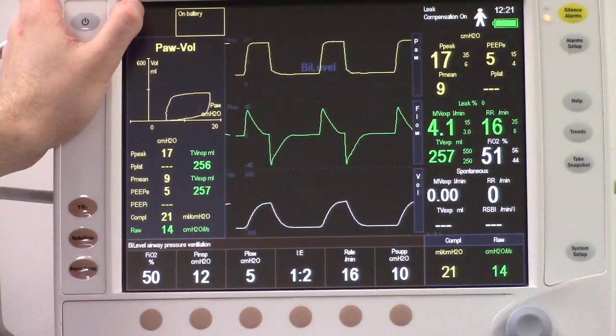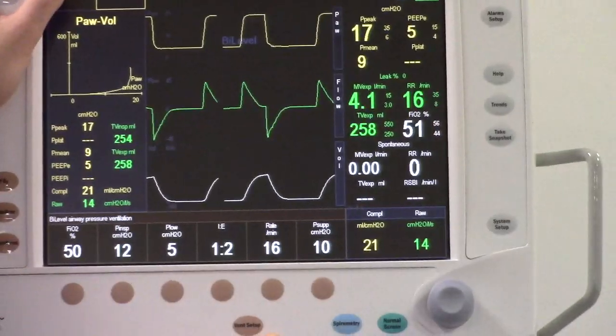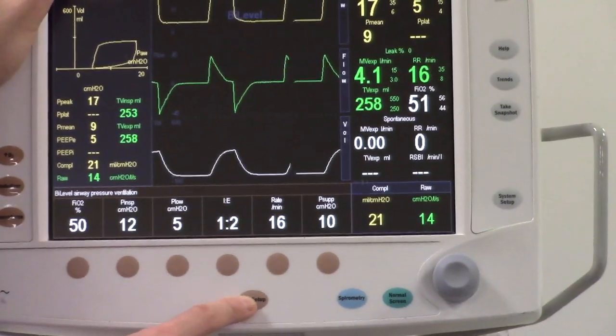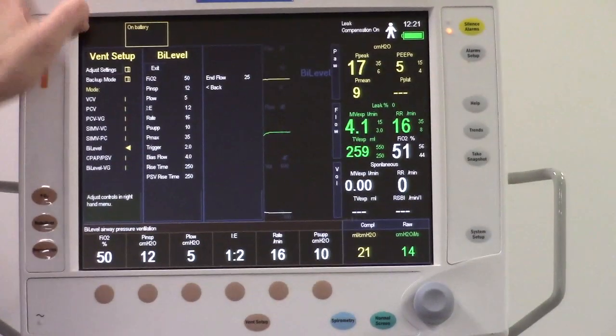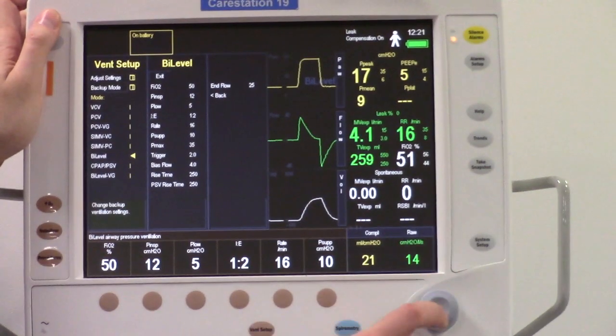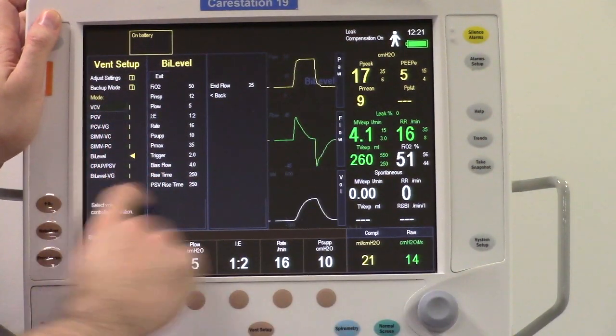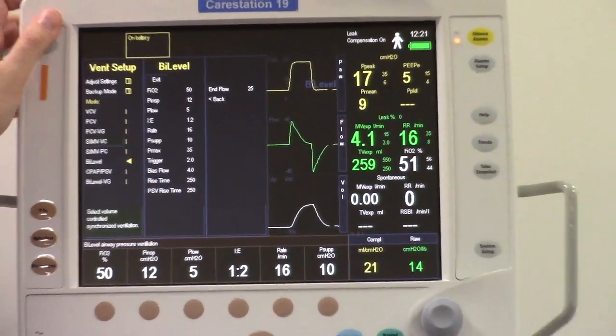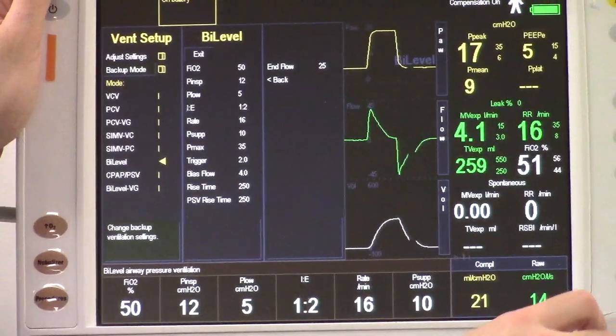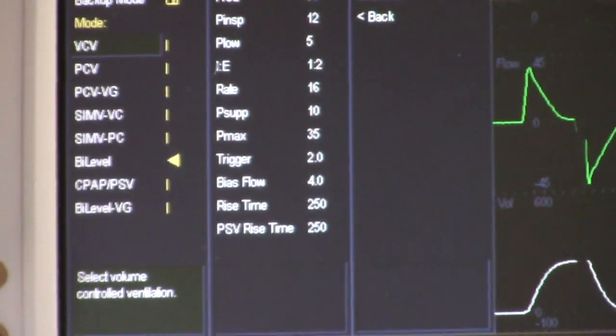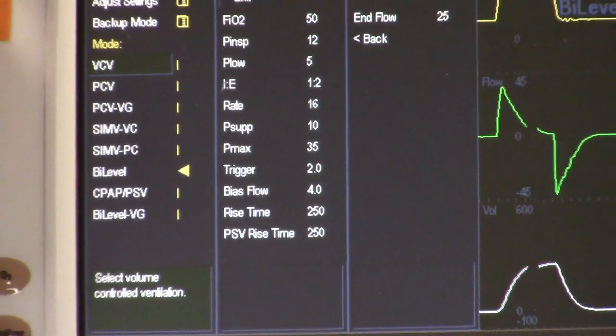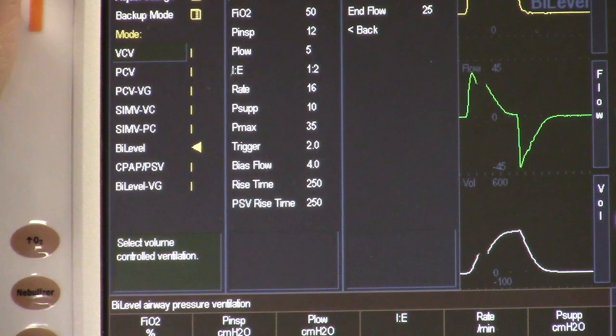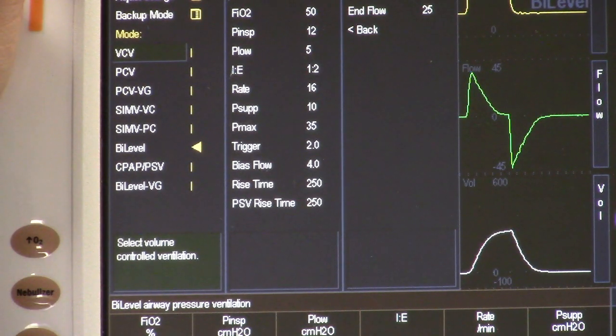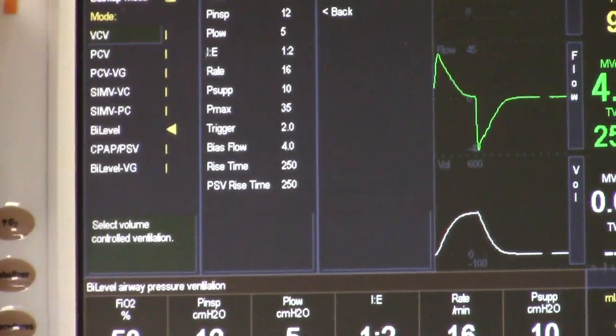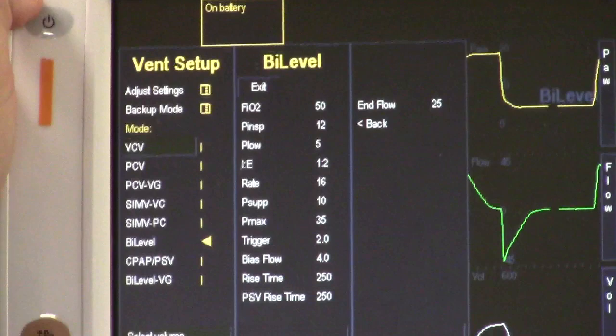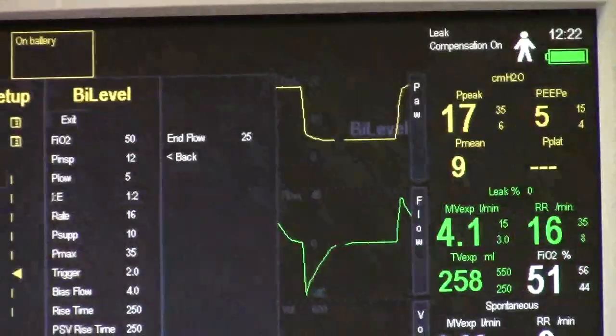So about the ventilation, everything you need to do about the ventilation is accessible via this button, Vent Setup. So if you press it here, you can select your mode from over here, yeah, as we can see at the moment we are on bi-level. So if you want to select, for example, volume control, do you know anything about the respiration modes? Okay, so there are mandatory and spontaneous. Mandatory ones are fully controlled by the ventilator, spontaneous ones are where the patient is actually putting in an effort and the ventilator is assisting.